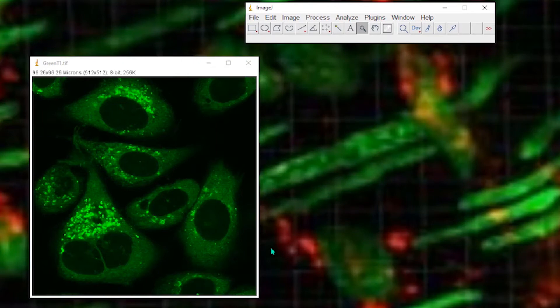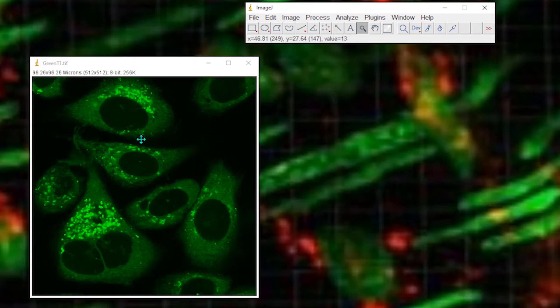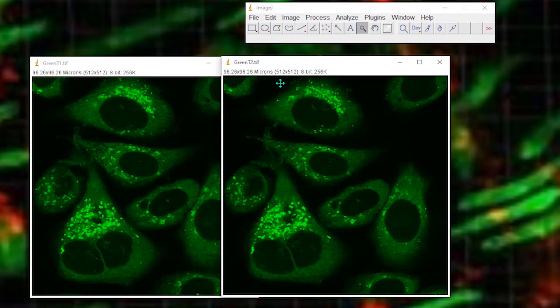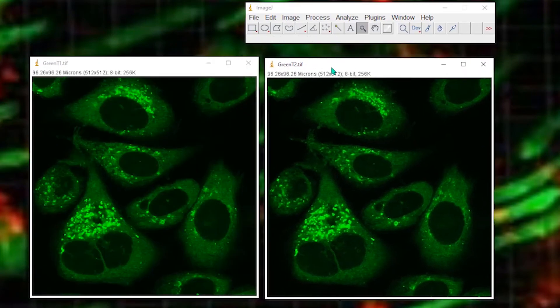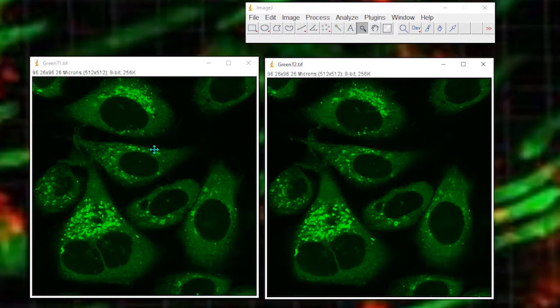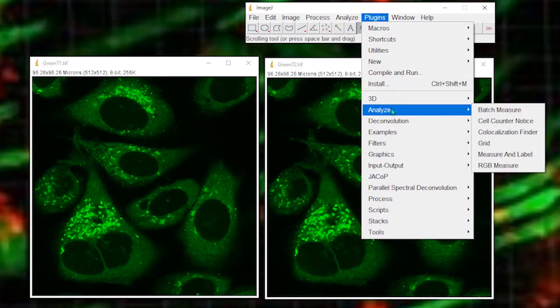The idea is that if there is no image noise, or very low image noise, if you took the same image at time point one and at time point two, they should be very similar — in fact, you would hope they would be identical. Here are two images. The only difference is that this is time point one and this is time point two. The image was taken on a confocal microscope, and then as soon as the image is taken, the image is taken again — so the only difference is a few seconds in time. Let's co-localize these two and see if there's a problem.